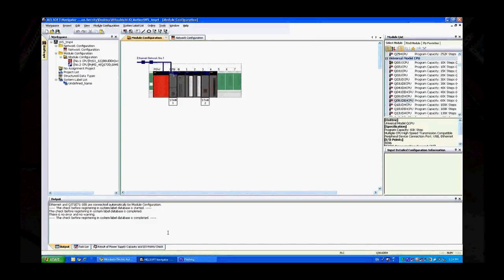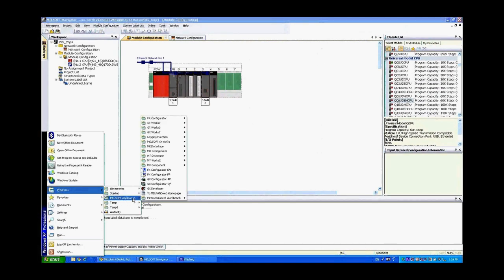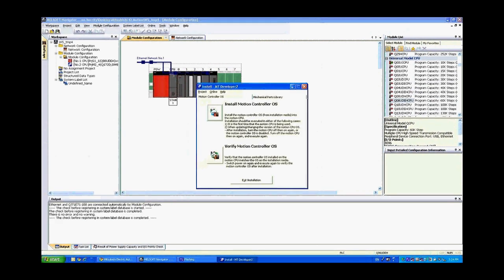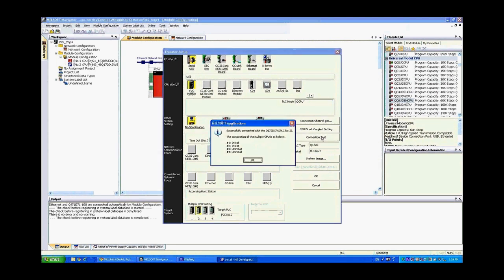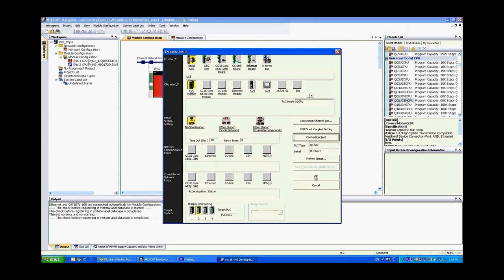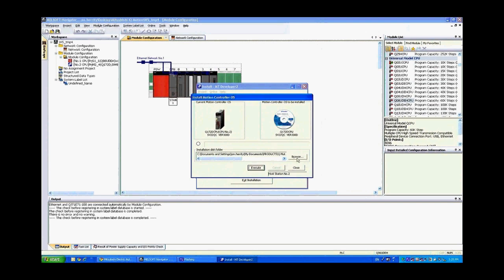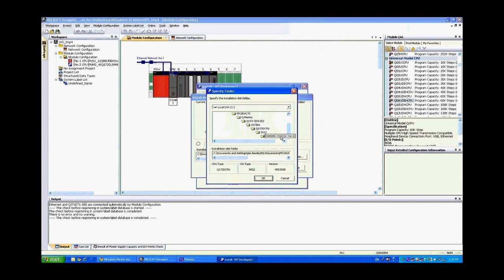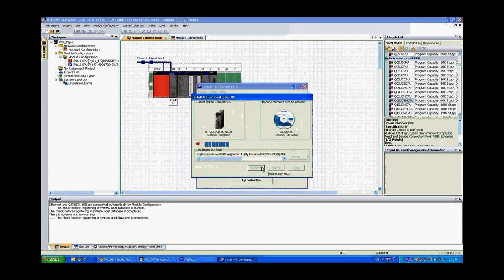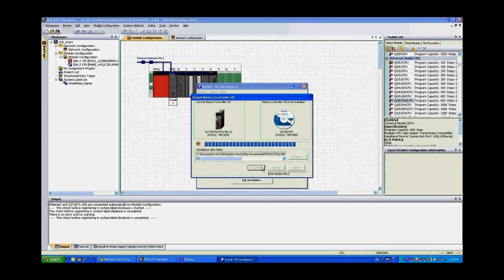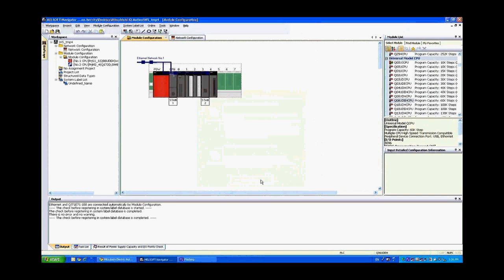Now in order to install the OS on the motion controller you go to the start menu, programs, Melsoft application and MT works 2. Here you'll see an option for install. Click on install. We're going to confirm our transfer setup. Go ahead and confirm that your USB PLC module, no specification to CPU number 2. Say connection test, you'll get successfully connected. Say OK, OK and then install motion controller OS. From here you're going to browse to your directory that contains that OS, click OK and then execute. Now it's going to download that OS file directly to the motion controller. And then click OK and then close and then exit installation.